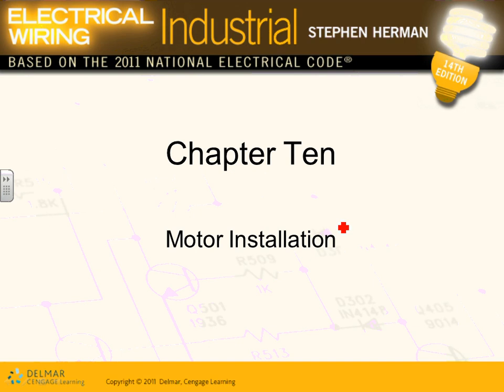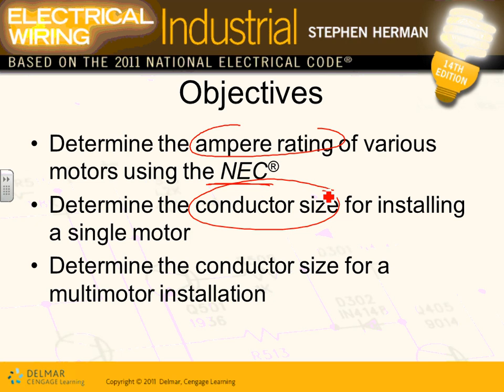Motor installation — now we know how motors work and how the control works, but how do you install these motors? You need to pay attention to determining the amp rating of various motors from the NEC code book. For motors, you use the amp from the NEC code book for everything except the overload.